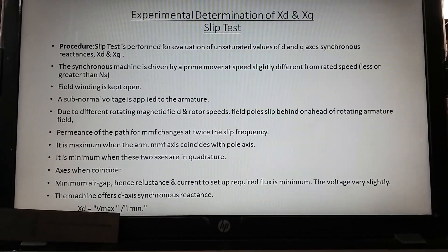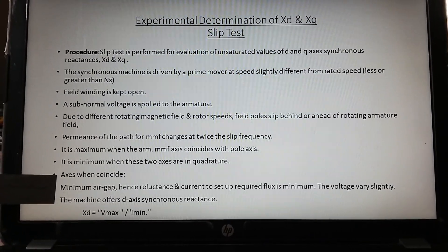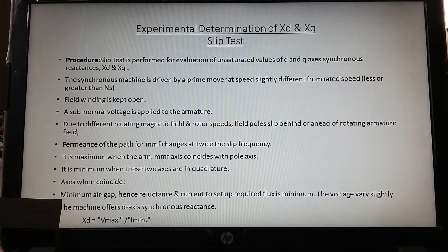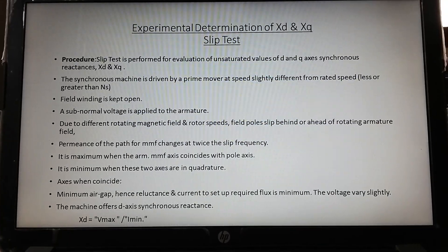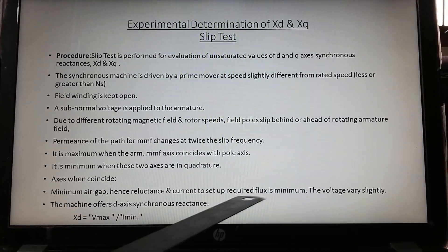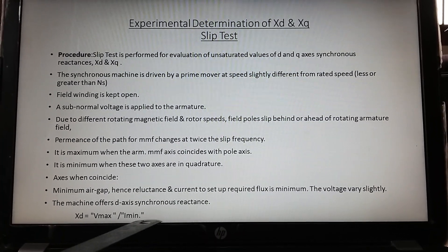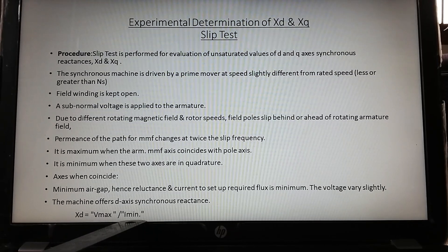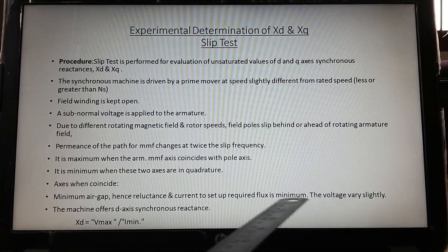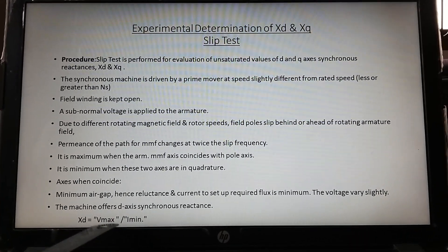Xd is equal to Vmax divided by Imin. When the armature axis coincides with the field pole, that is along the d-axis, there is minimum air gap between the two parts. Minimum air gap means the reluctance required to set up the flux will also be minimum. That is why the armature current is minimum. Because the current is minimum, the voltage drop will also be minimum, so the voltage will be slightly higher — that voltage is referred to as Vmax.